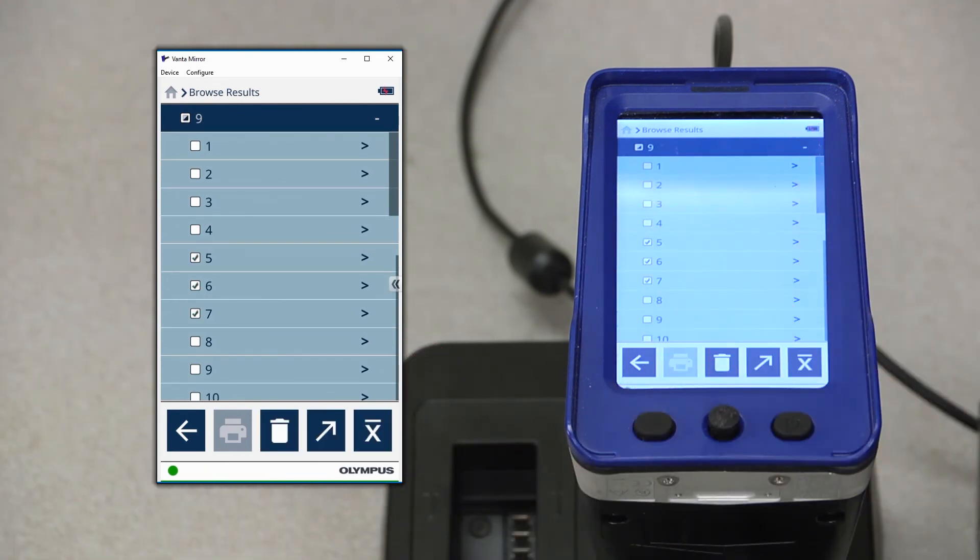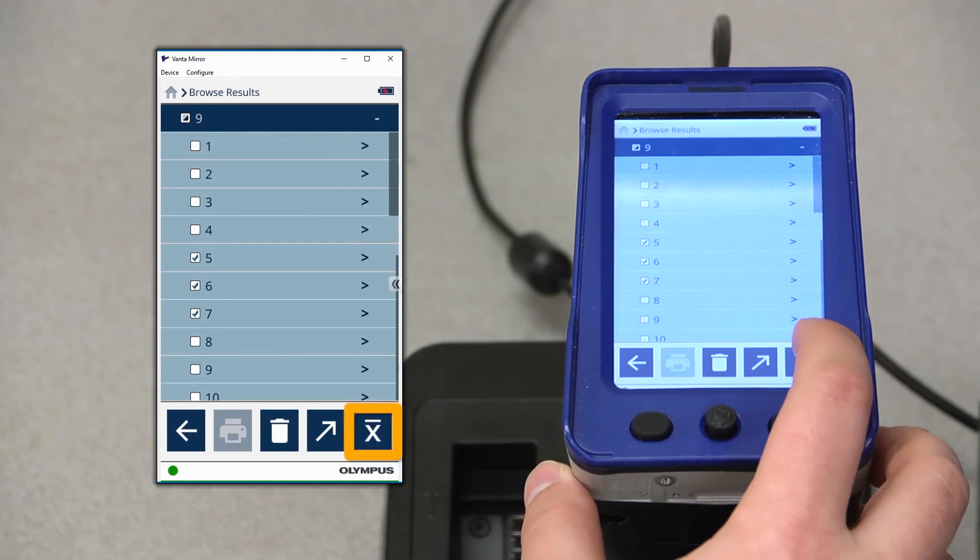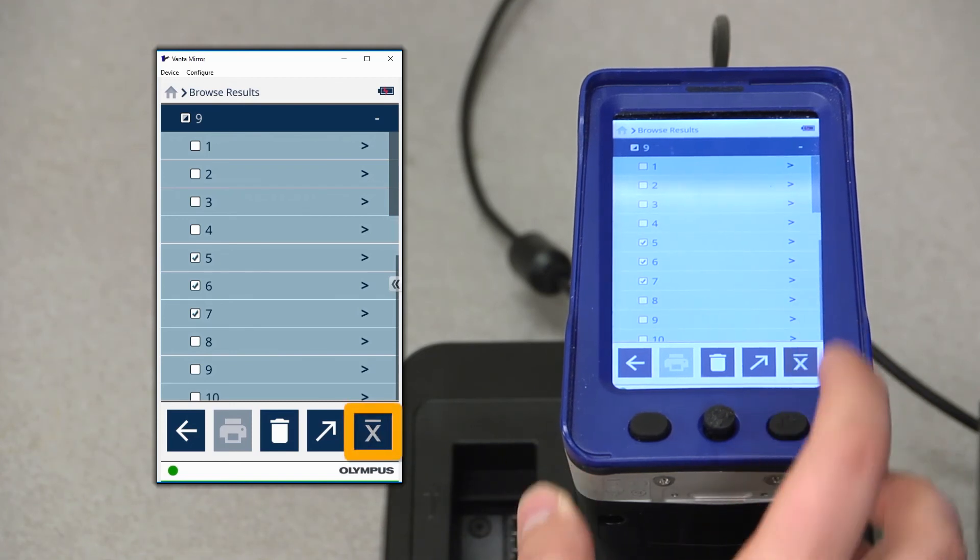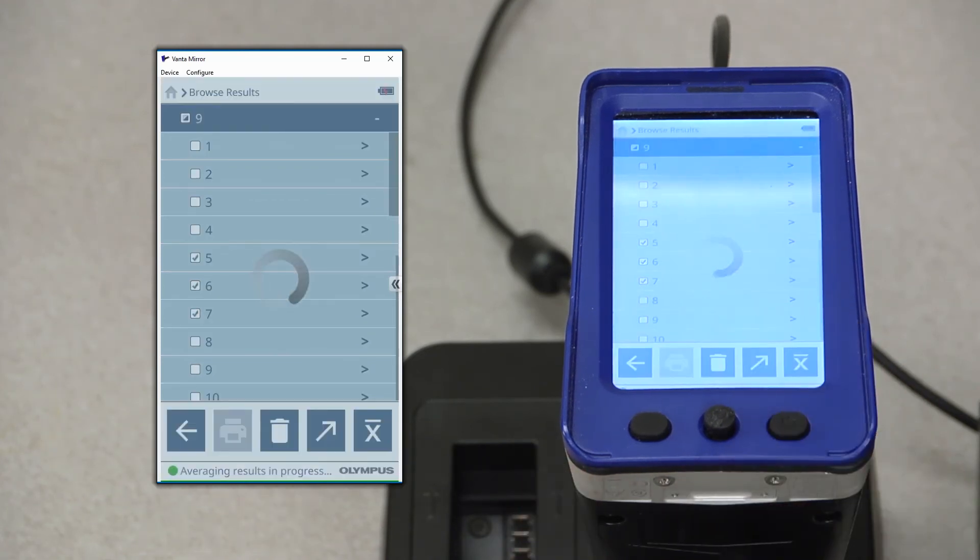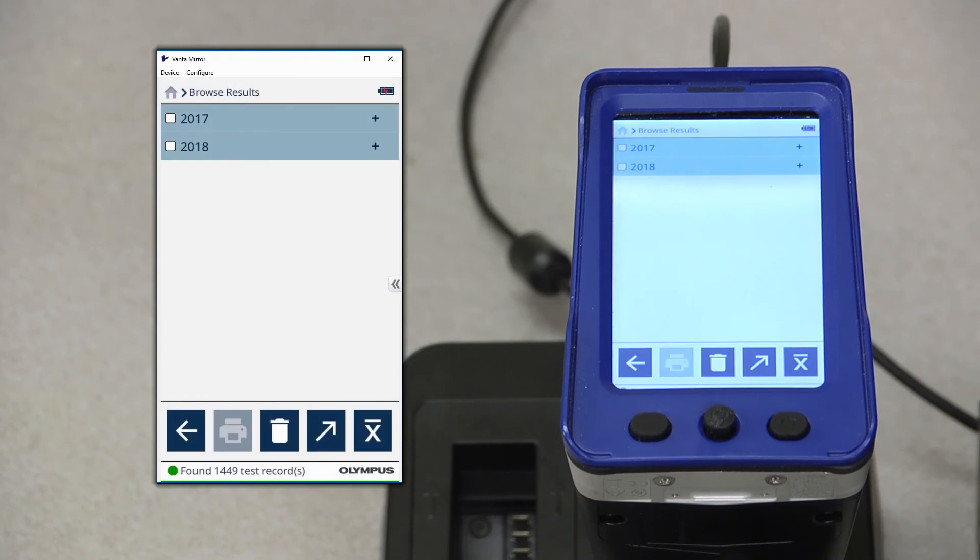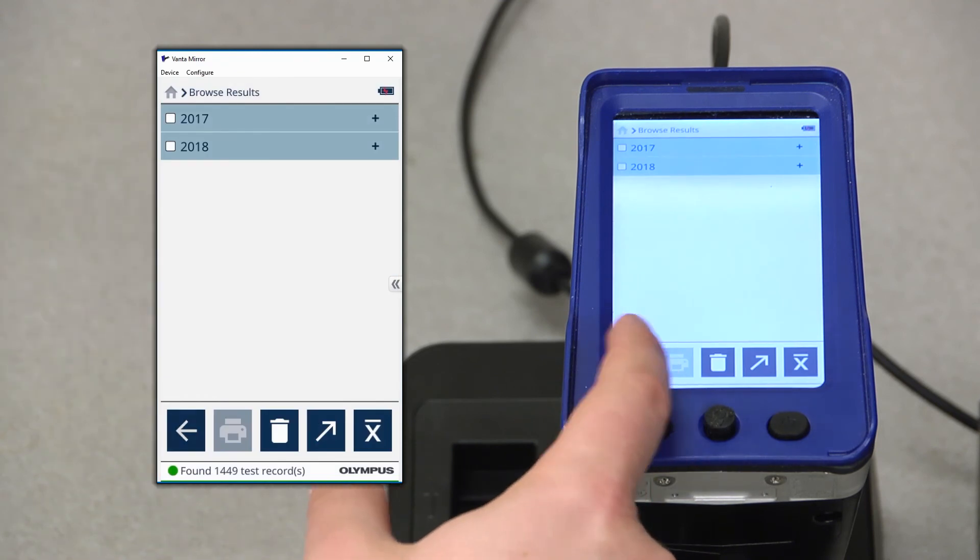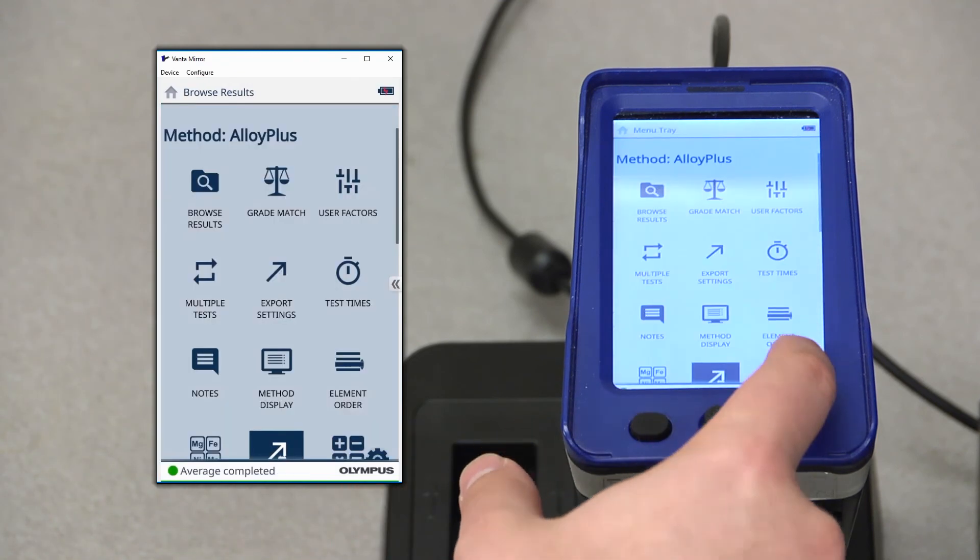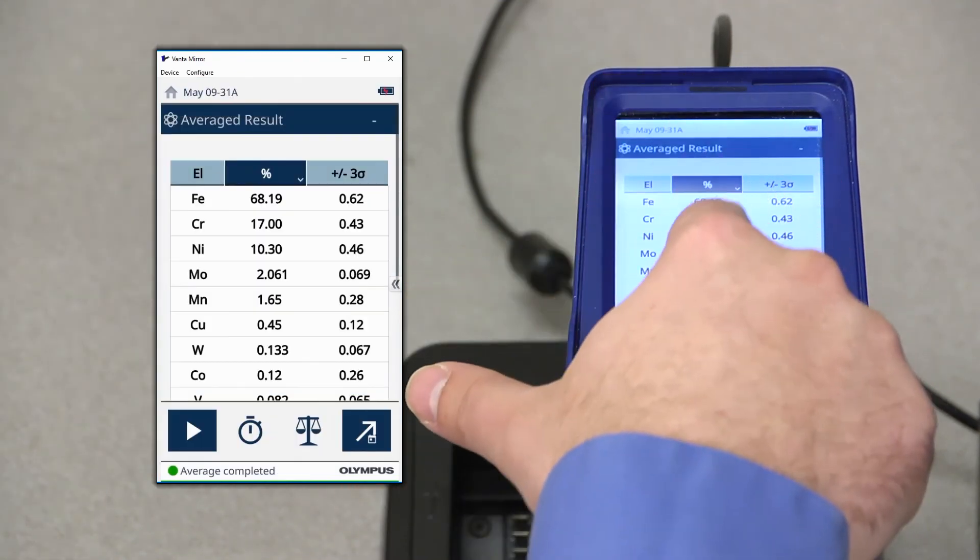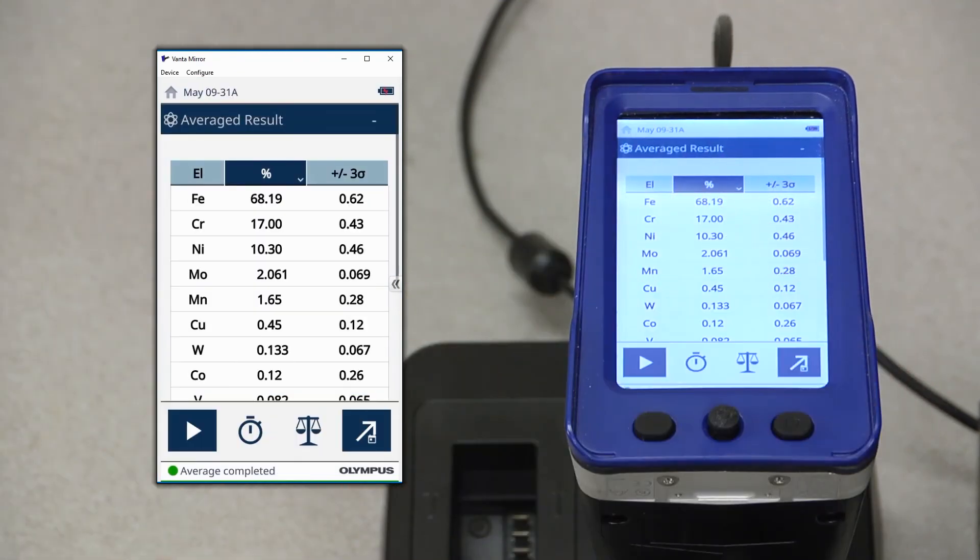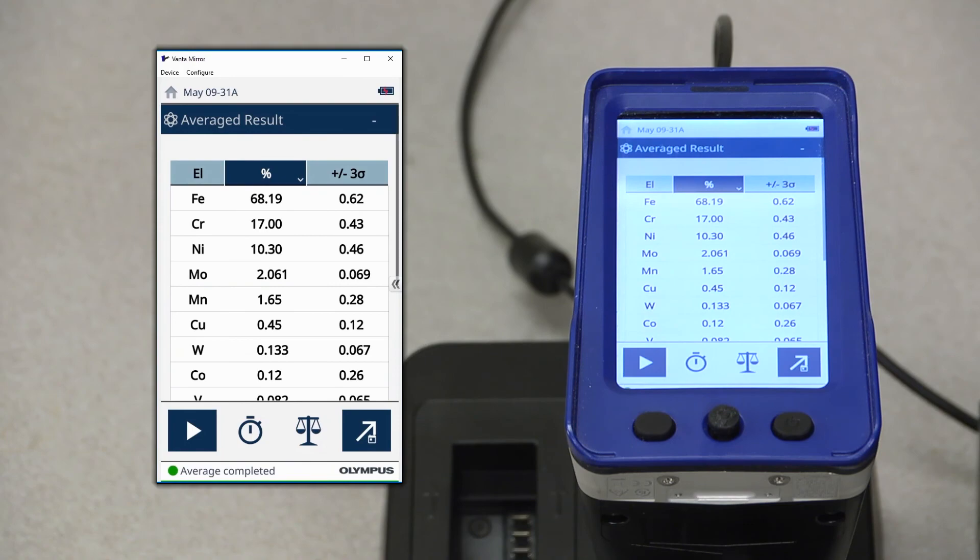When you select the results that you want to generate an average of, press the averaging icon in the bottom right-hand corner. And with that, we've generated a new average result. And that's it. That's how easy it is to generate an average result on your Vanta handheld analyzer. Thanks for watching.